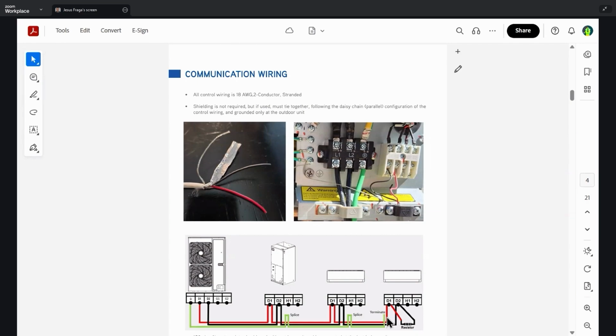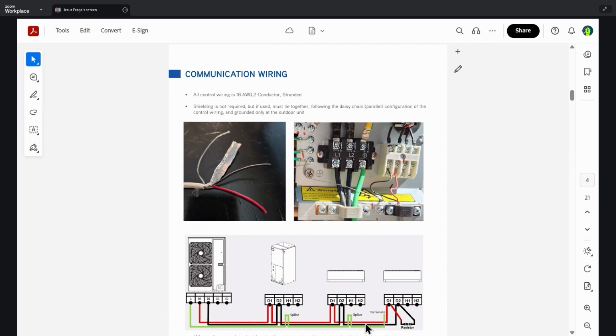Now, this doesn't mean that we're going to land these wires in the middle of the communication chain. With splicing, we grab the ground going to the next unit and the ground coming from the next unit and splice them together here, and here, and only terminate at the last point of contact in that data chain. This gives one path for interference, if there ever is any, in this communication data chain. So if there's some type of communication fault or a ground, it'll travel its way out to the outdoor unit and terminate there, and not in between in the data chain communication.